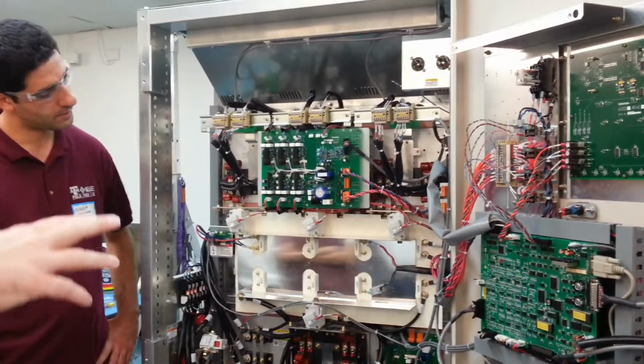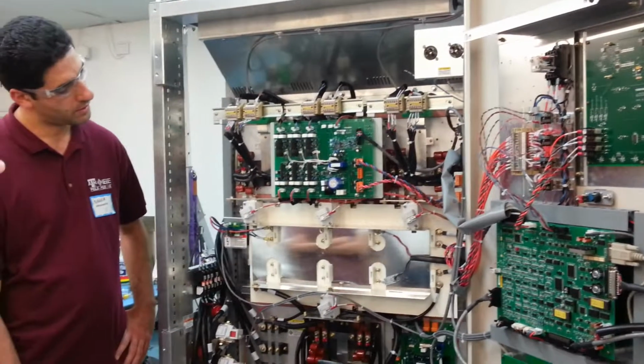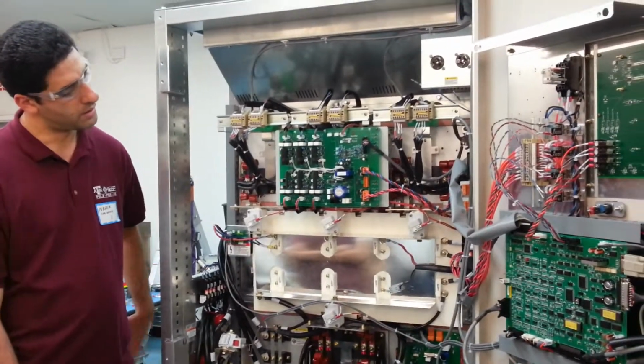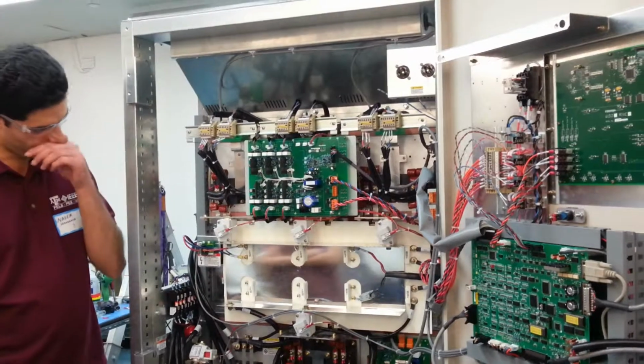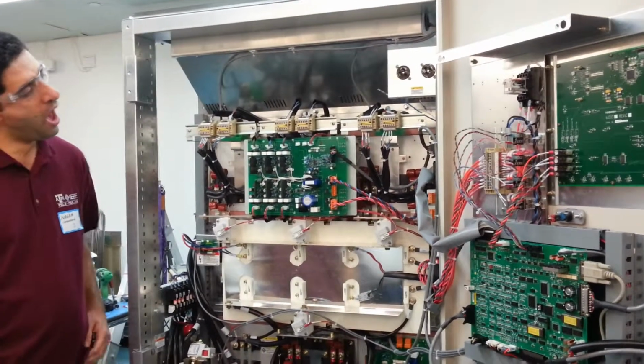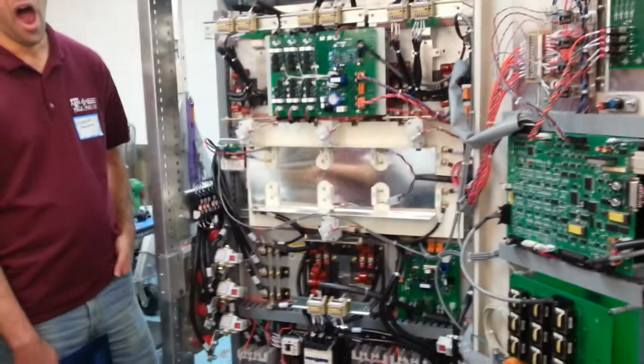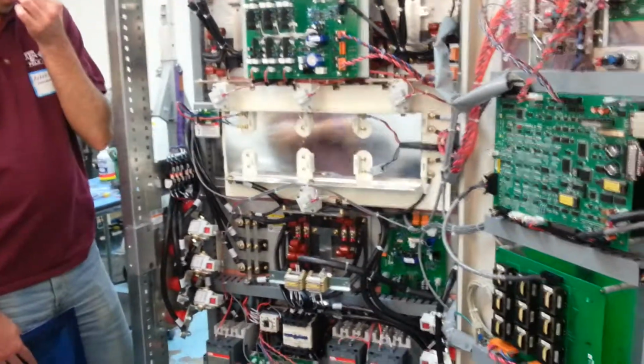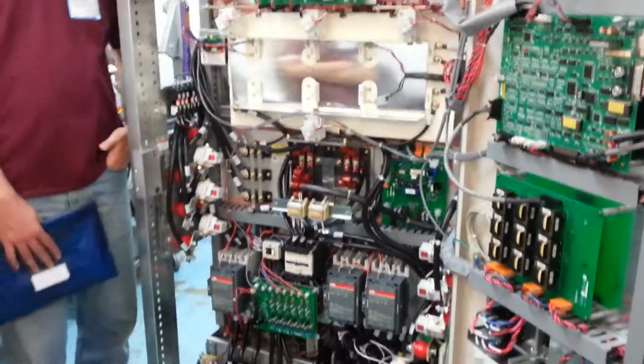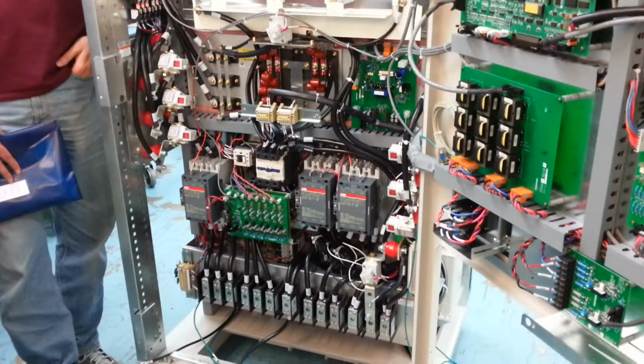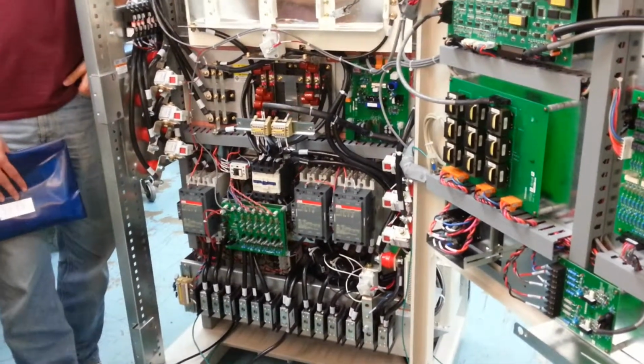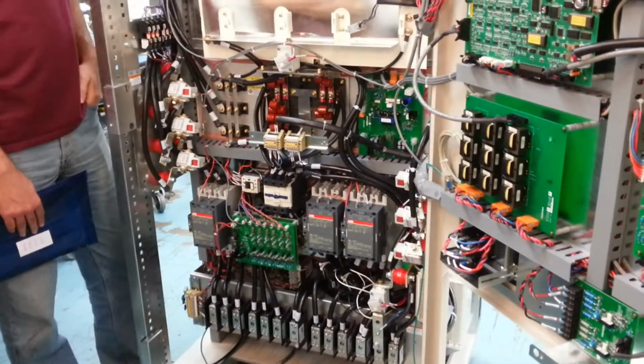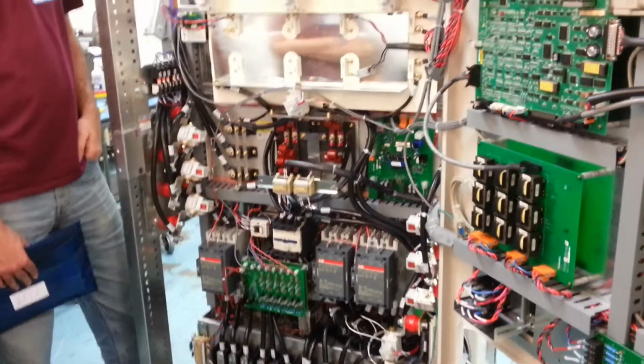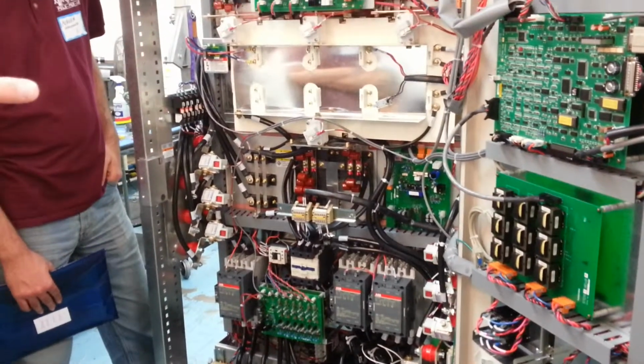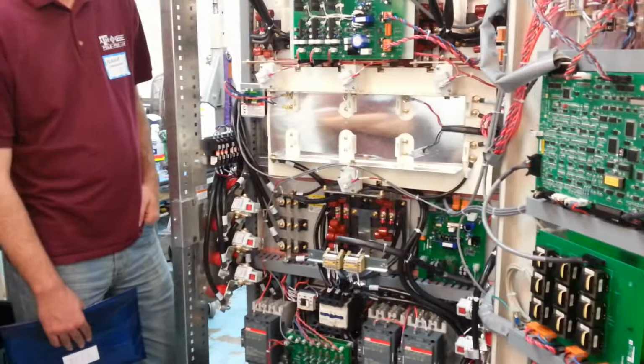Those 2, 4, 6 IGBTs on top. Driver boards in the middle. And then the PWM coming out the top is forced through the panel into the transformer. And then, of course, sinusoidal is when you add an LC circuit, which turns it into a sinusoidal waveform and produces a 480 volt output. So same kind of thing flows through: rectification, DC bus, inverter. And then we have our driver boards, control board, display, and all of our power supply boards.